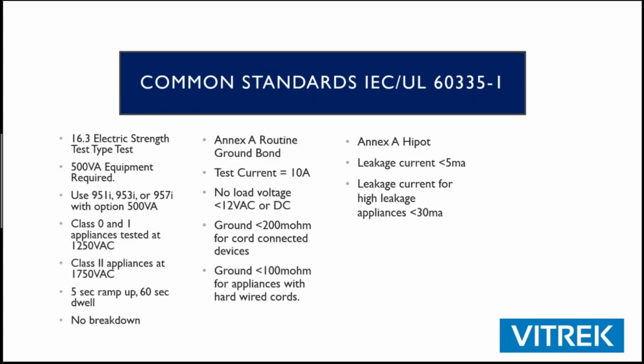All right, so this is one of the most common standards, 60335. It often requires you to have a 500 VA output transformer. That's something that really confuses a lot of people. They're like, if my product is tested at 1,000 volts and only draws 5 milliamps, 5 VA, why would I need a 500 VA output rating? And that's kind of a legacy standard.